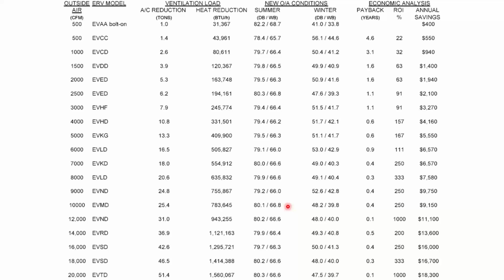This is a cheat sheet chart. I did it. It's the first time I ever said it on the first try. Cheat sheet chart that we made years ago. I'll give you a couple examples off it. We don't have time for the whole thing. But if I take 1,500 CFM of outside air, which is a pretty good amount, and I run it through a specific ERV that I selected here, it is going to mean that I need 4 tons less cooling than I was going to get. If I needed a 15-ton unit, I'm now in the market for an 11-ton unit, right? I'm going to need 120,000 BTUs less of heating. So I'm looking for a smaller hydronic coil or a smaller gas heating section.